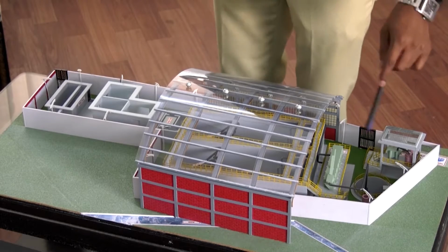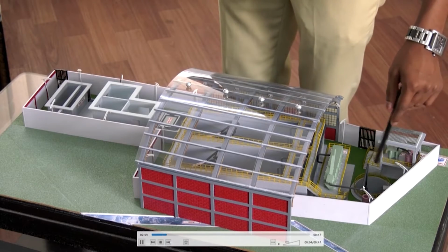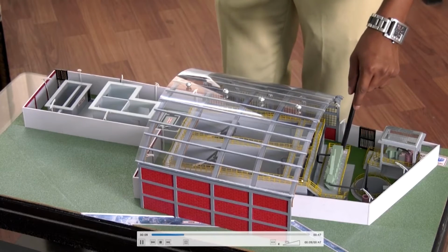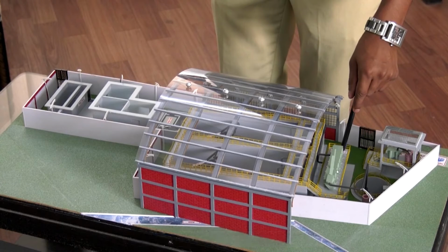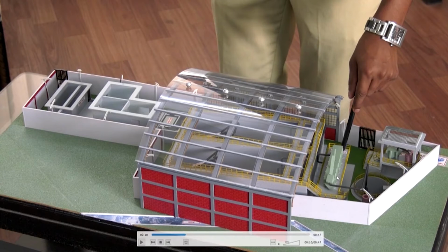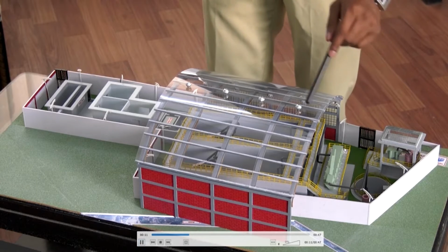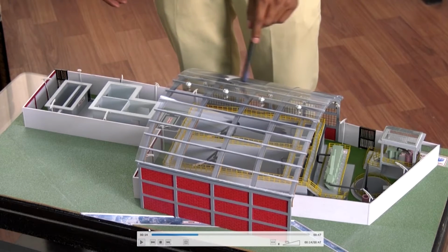So, a brief overview. Here we have the sump where all the wastewater is going to be collected by gravity. It goes to the primary treatment here, but in this primary treatment we are not looking at sedimentation tanks or such to remove suspended solids. We are only looking at coarse screens and grit removal, right? But again, I think they are calling it by a trade name. So, that is what we have. It is not the typical primary treatment. And after this primary treatment, the flow is coming out here, let us say, from the sump, and obviously this is at the lowest level.